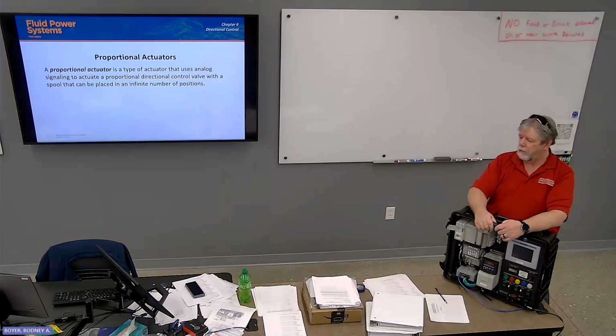Proportional actuator is a type of actuator that uses an analog signal to actuate a proportional directional control with a spool that can be placed in an infinite number of positions. That is something of a misnomer because there's no such thing as infinite when you're talking about analog control. But it can essentially be anywhere in the range.